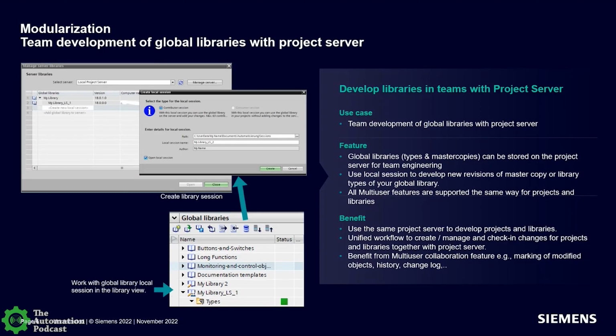The libraries that exist in the palette on the right side, there are 2 types: either the project library for user-defined data types or faceplates or objects that you want to apply across the devices and hand to the customer as objects that are built into the project, or the global library, which is our standards. We define standard blocks associated with control of a drive, control of an interface to the upper level system, or a faceplate for the HMI, and we put those into our global libraries and we start working together. And again, as I mentioned, those libraries, which are inclusive with the framework of the TIA Portal, are not an add-on licensed functionality with the TIA Portal. It's just part of that ability to do automation libraries.